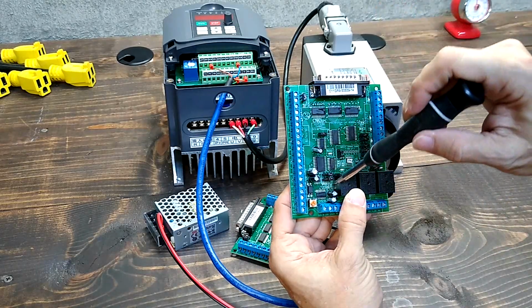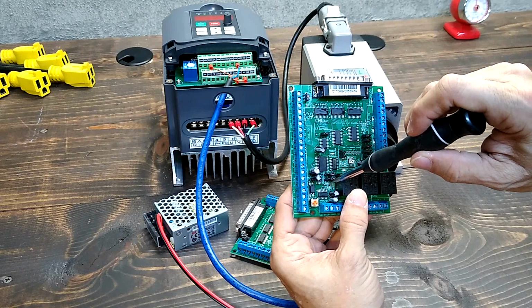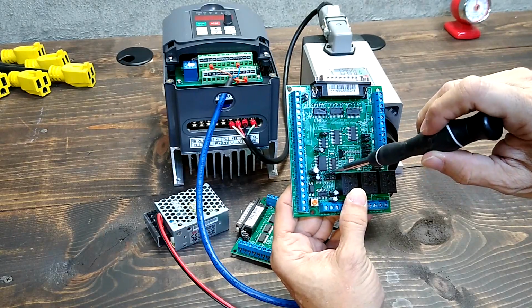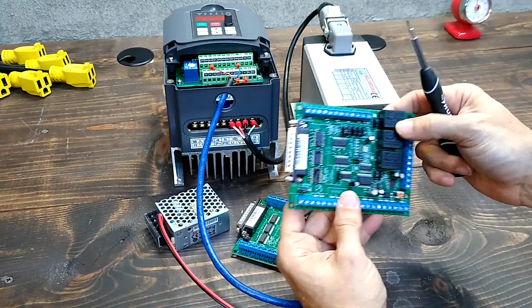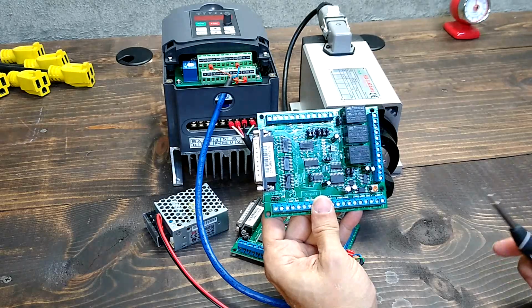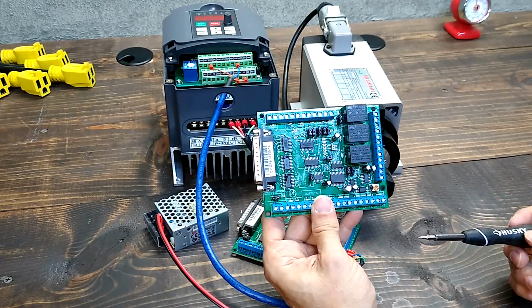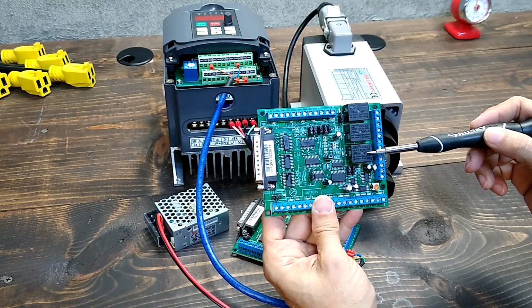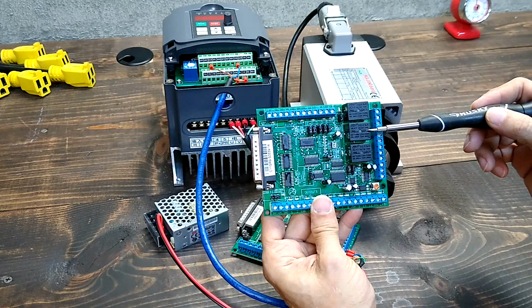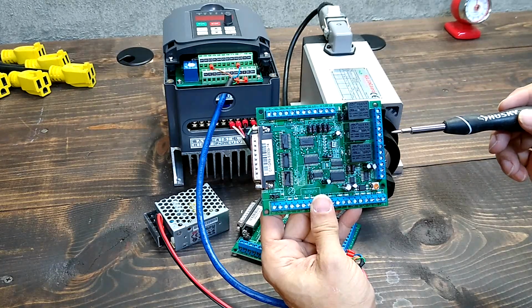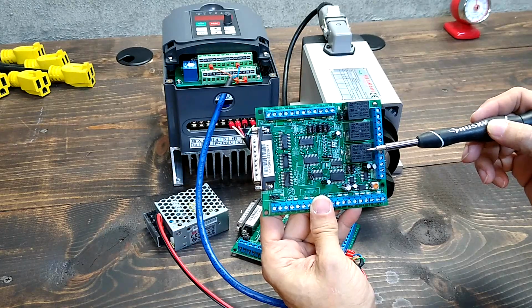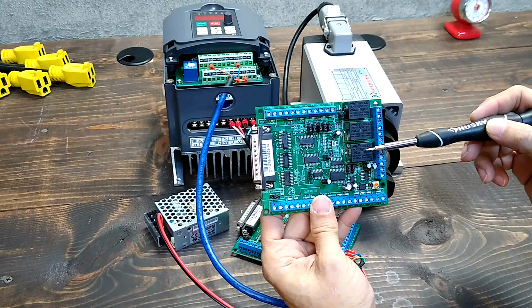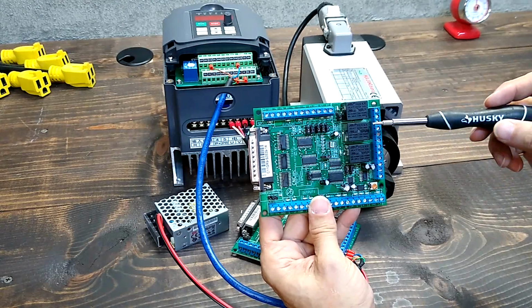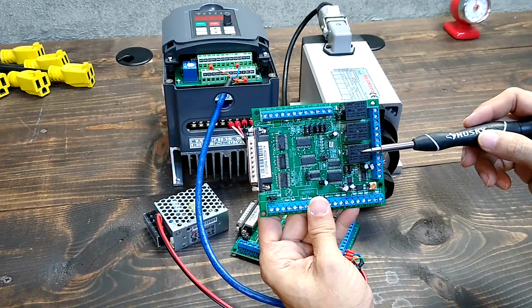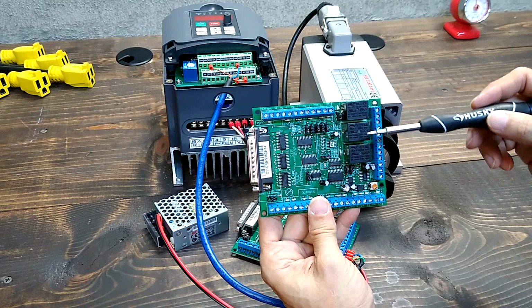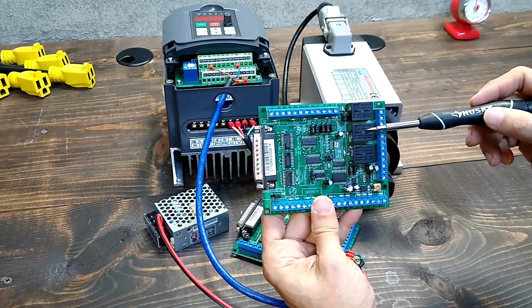We have international and US mode. For US mode, relay 1 runs clockwise and relay 2 runs counterclockwise. On international mode, relay 1 turns spindle on clockwise and relay 2 will determine the direction. It will basically run counterclockwise when both relays are on. We will be setting jumpers to international mode, since we will only be running spindle clockwise, and we will be able to use relay 2 for any other connection like vacuum or cooling connection.